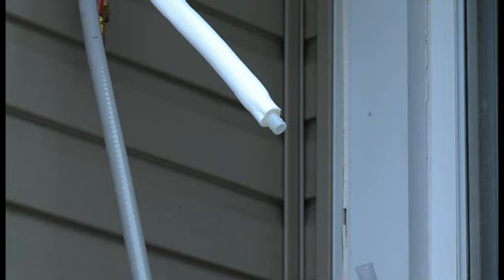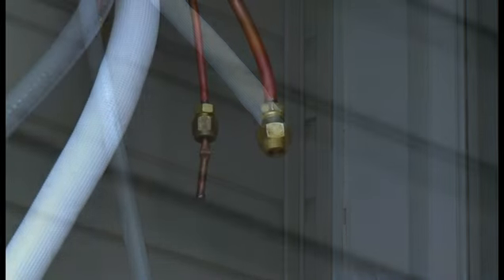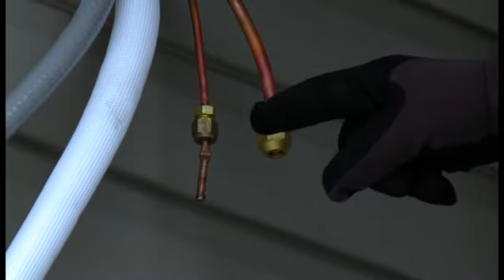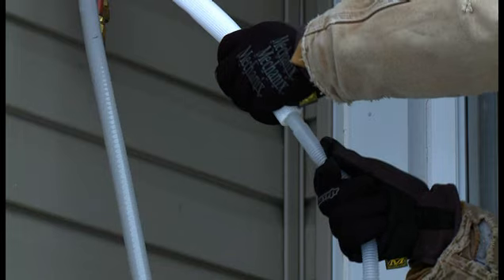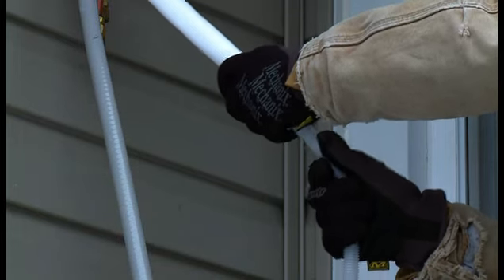On the bottom of the unit is a drain hole. Insert the drain connection into the drain hole. If your unit has additional holes, cap these holes with the drainage plugs provided. Now, install an extension drain hose to the drain connection. Make sure the water drains away from the structure. In these next steps, we'll attach the drain hose extension, as well as the liquid and gas refrigerant tubing. Begin by attaching the drain hose extension.